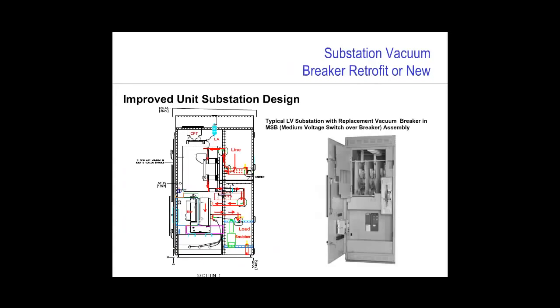We spoke earlier about installing a vacuum circuit breaker in an existing assembly, but what if it was a new assembly, either for an existing substation or a new project? In this case, we can apply a medium voltage switch over breaker, or an MSB. This assembly is functionally identical to the retrofit assembly we reviewed earlier. It has a load break switch, visible blade in the top, and a fixed mounted vacuum circuit breaker in the bottom.